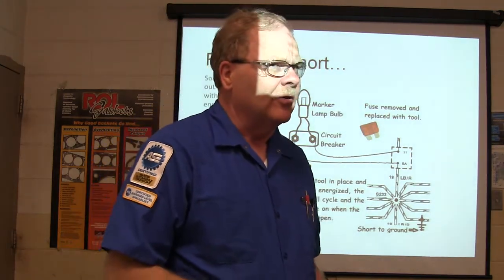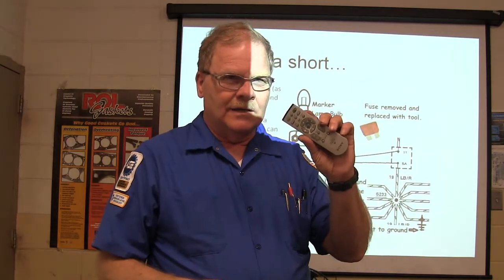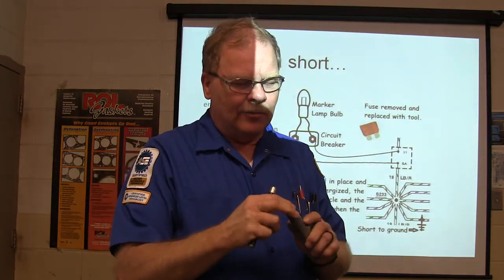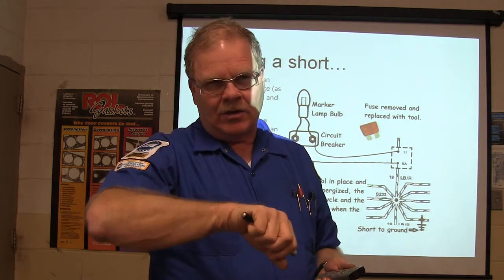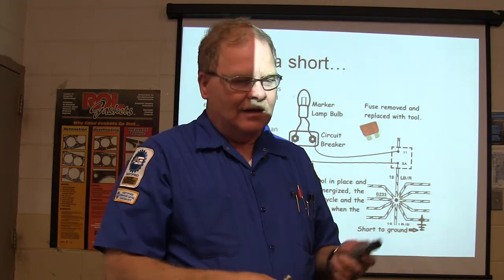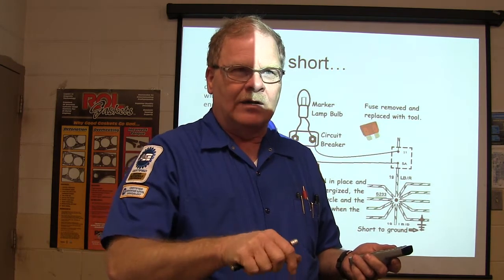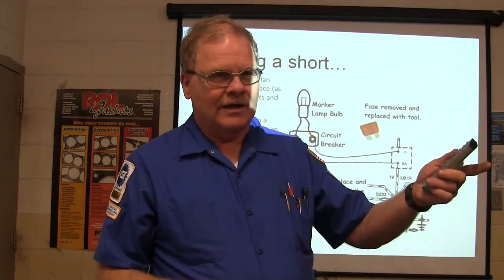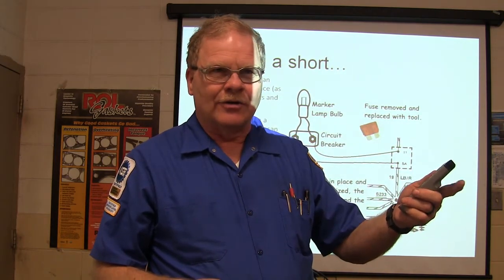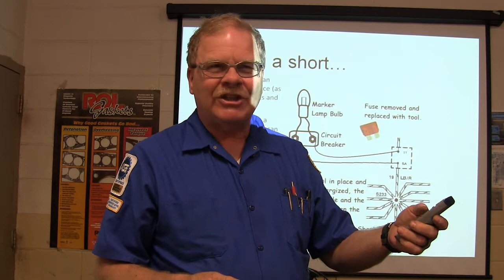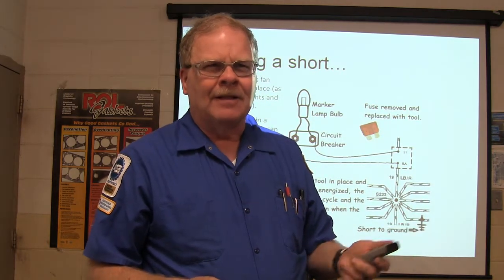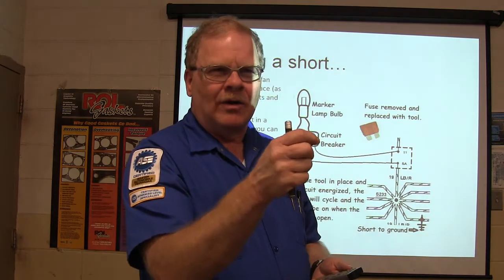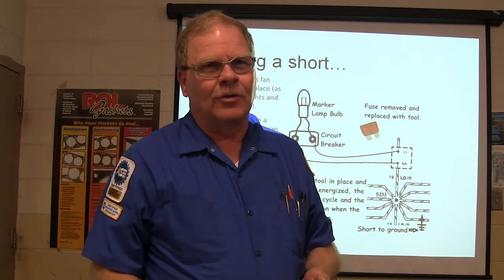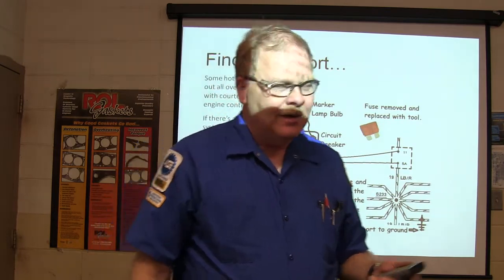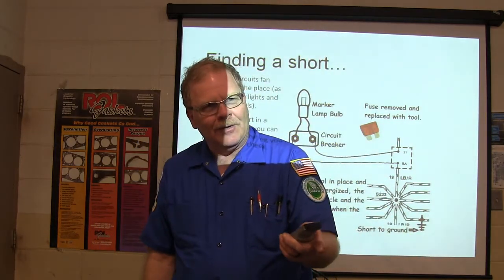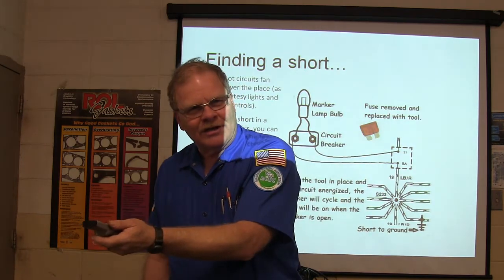Something else you can do that most people don't know about: take a remote, like this one. They put out some noise if they're poorly shielded. So turn your AM radio all the way down to the low end of the band, it's real susceptible to static. Turn the volume up, go over by the radio antenna, wherever it happens to be, and pull the trigger on your remote, an old TV remote, and it'll make static. Then go to the fuse that's blowing and get on the side of it that's feeding the circuit where the short is. While the radio's on, walk down where you know that wire goes, pulling the trigger on the remote. When you get to the place where the short is, the radio will go.